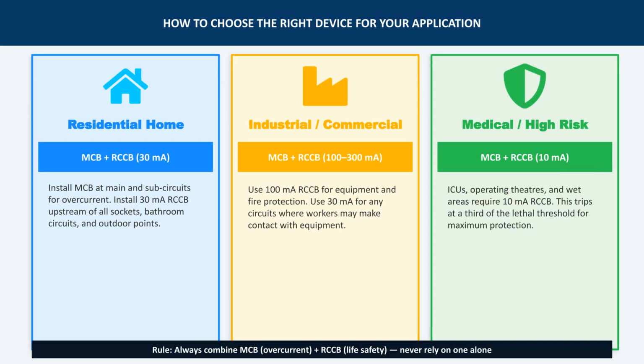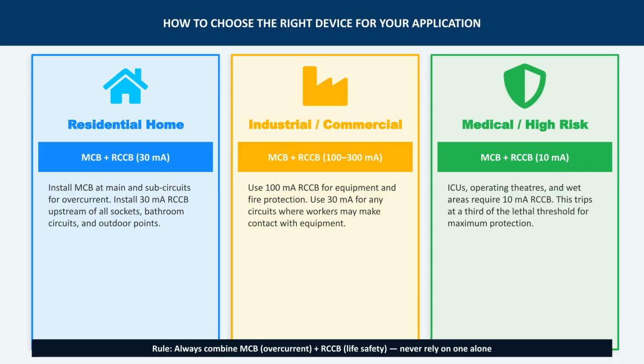For residential homes, install both MCB and a 30 milliamperes RCCB. Industrial settings use 100 to 300 milliamperes RCCB for equipment and fire protection, with 30 milliamperes for human contact areas. High-risk medical areas require high-sensitivity 10 milliamperes RCCBs. Always combine MCB for overcurrent with RCCB for life safety.